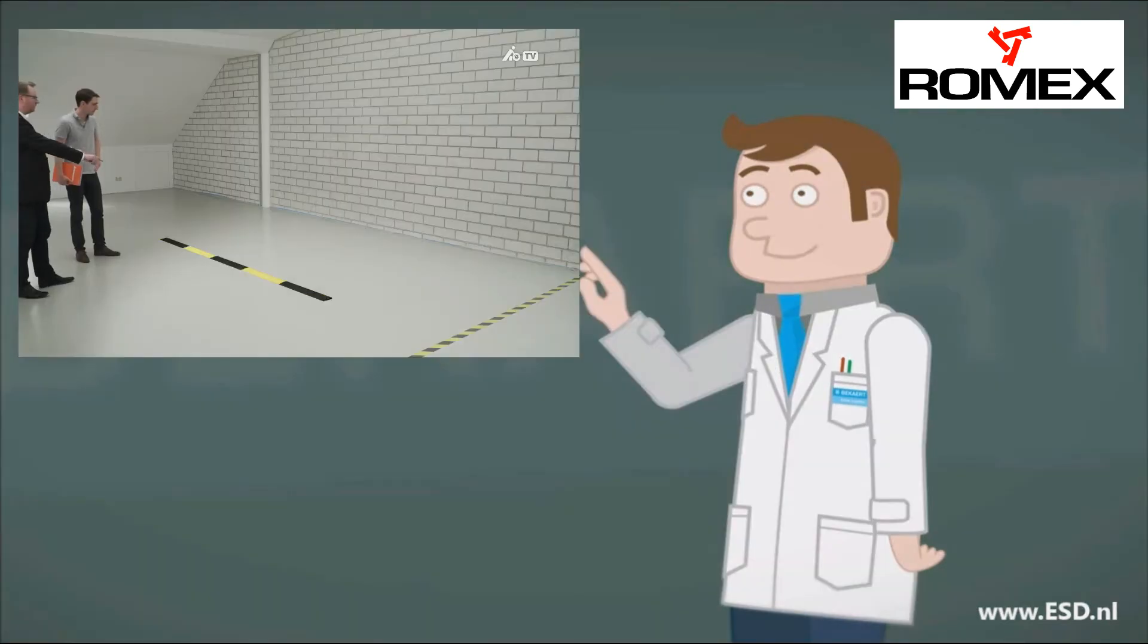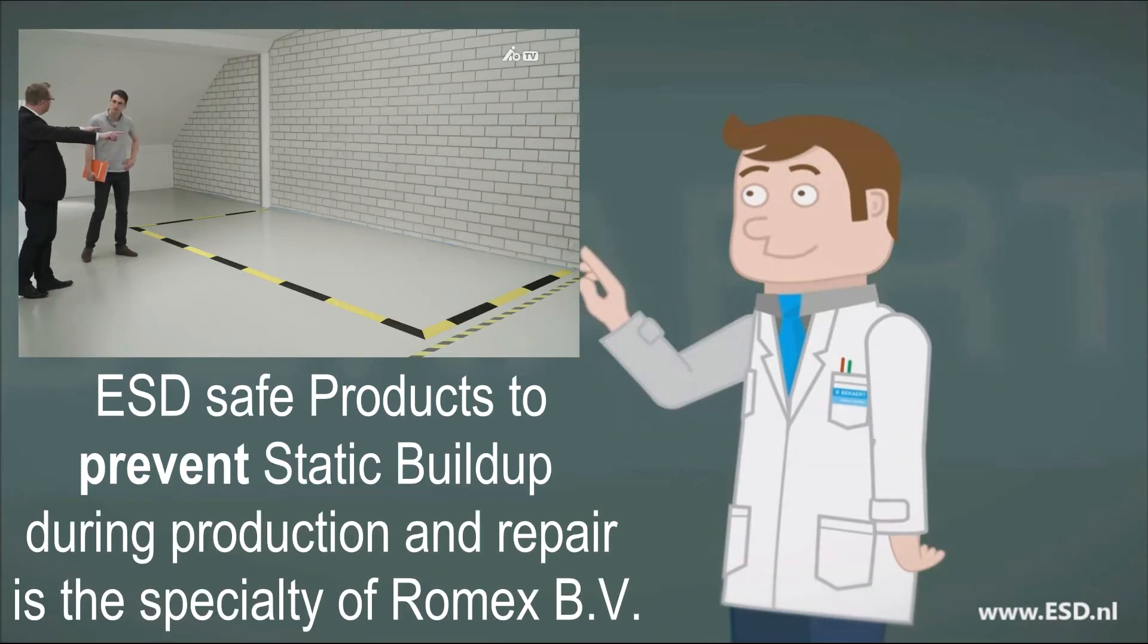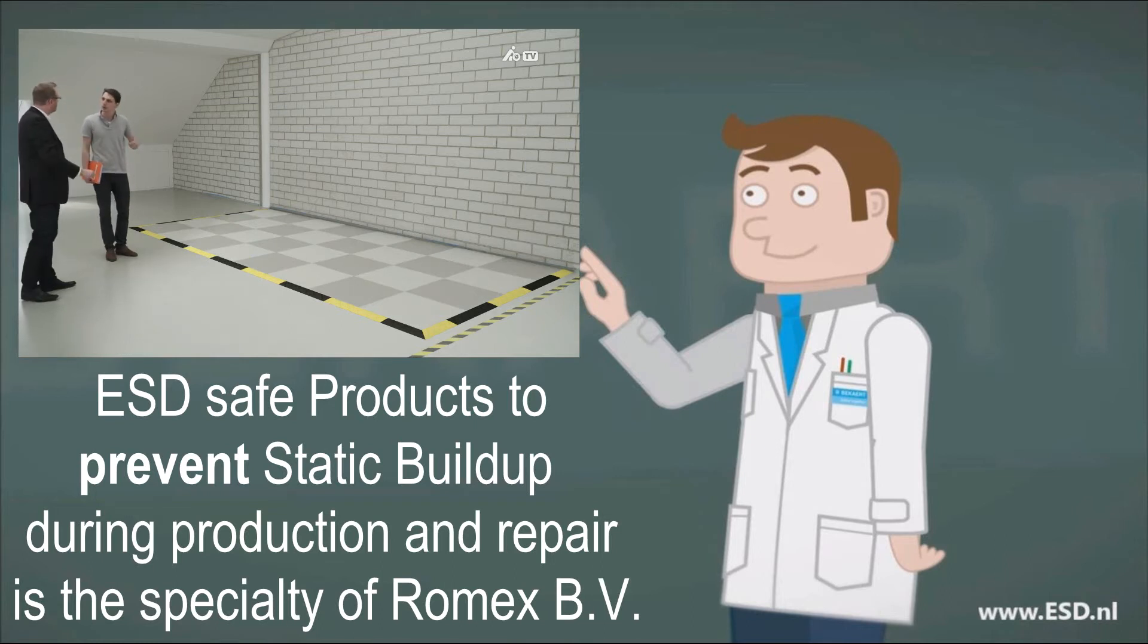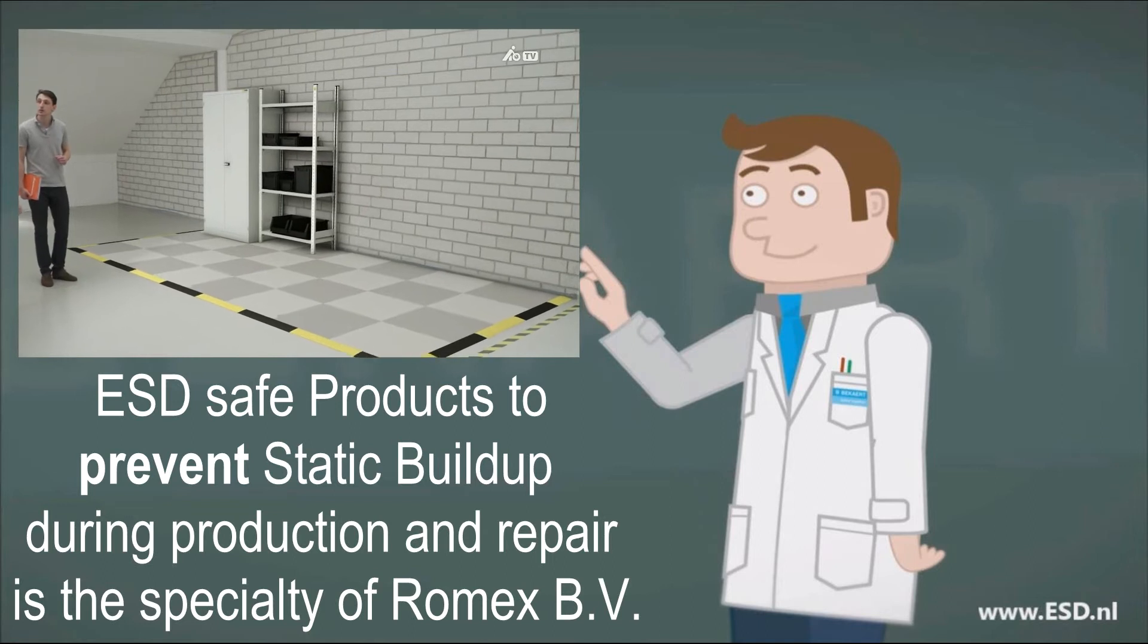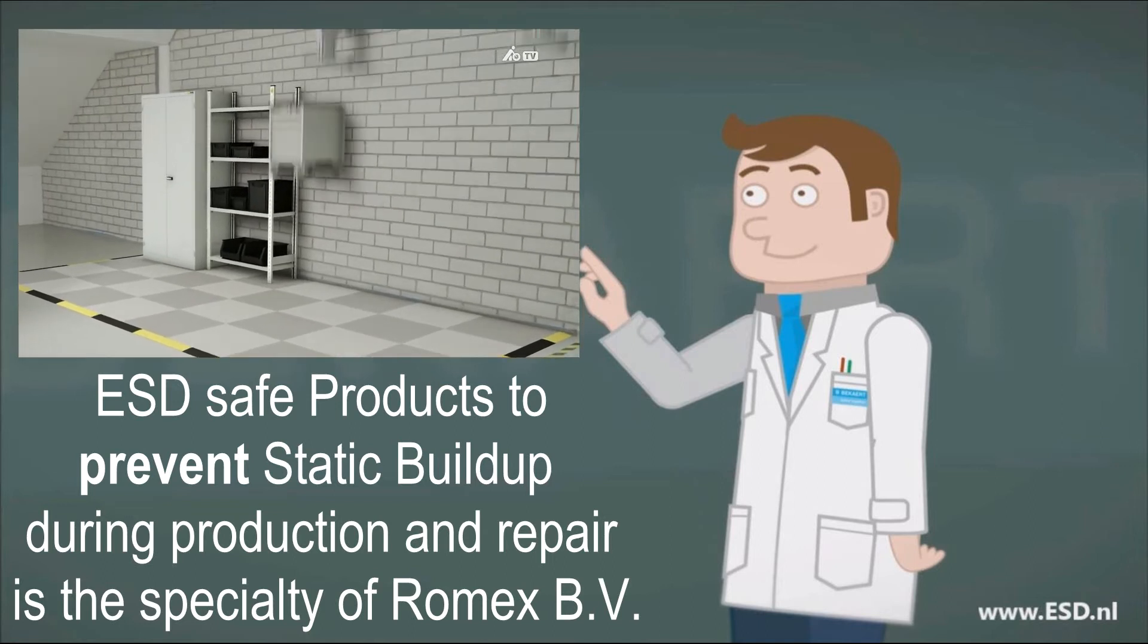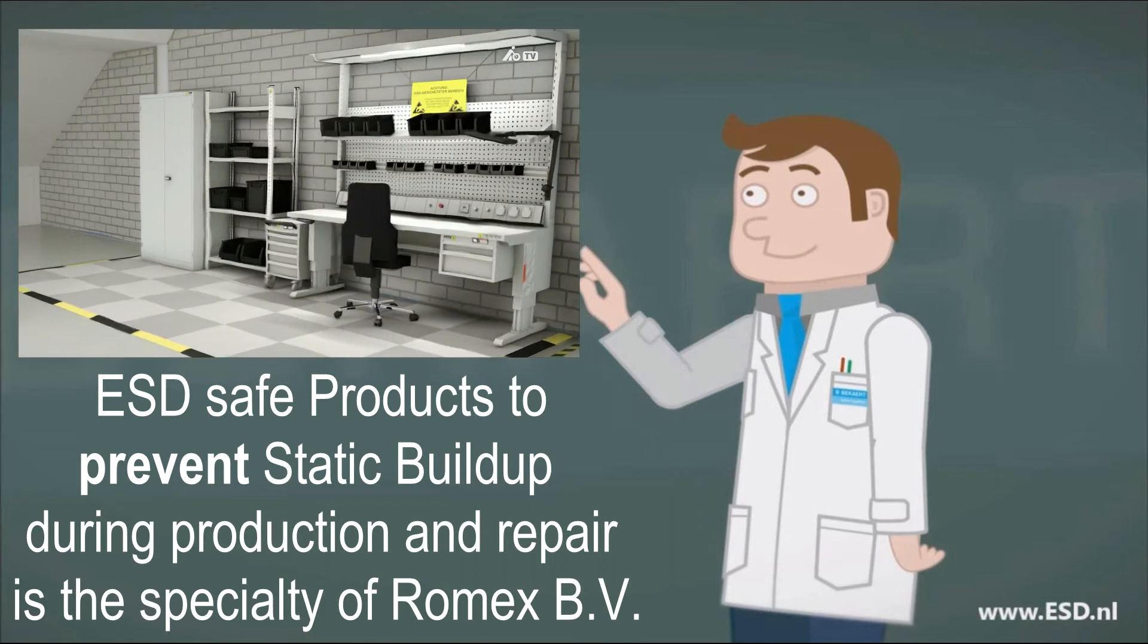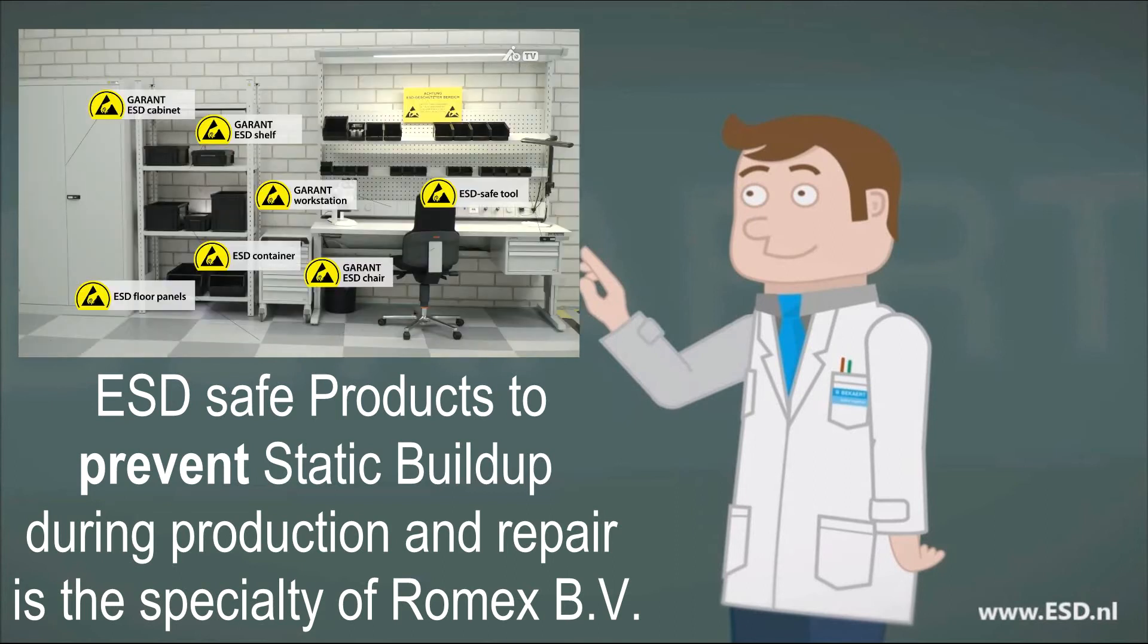The EPA must be identified as such for all employees so they do not inadvertently trigger ESD events on sensitive devices. However, when planning your EPA, we will not only focus on the necessary EPA components but also on the best design for your workstation in order to improve efficiency. Workstation, shelves, cabinets, and floor must be connected from the grounding points to a suitable ground in the building.